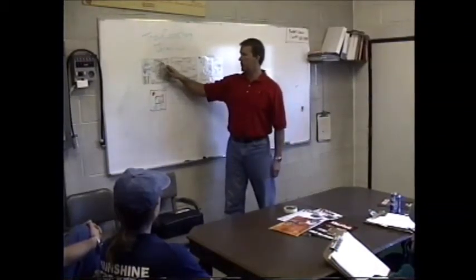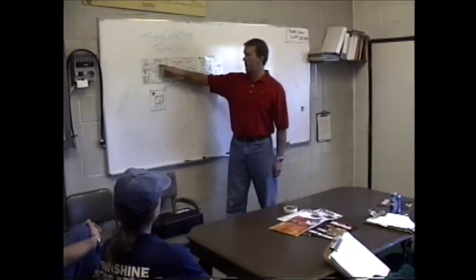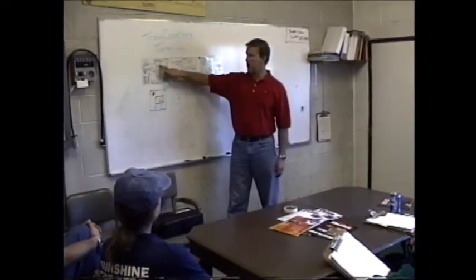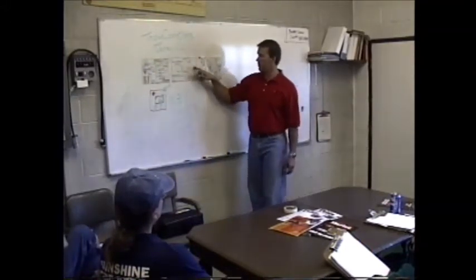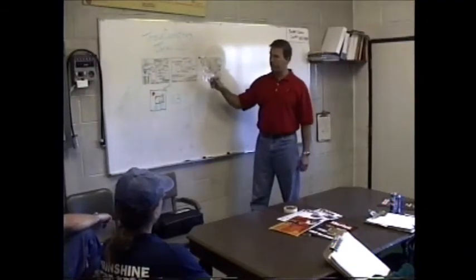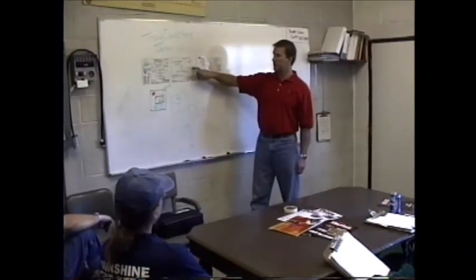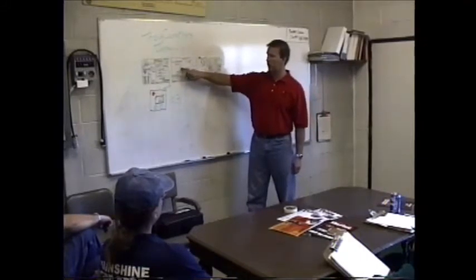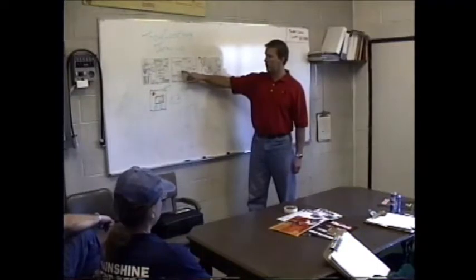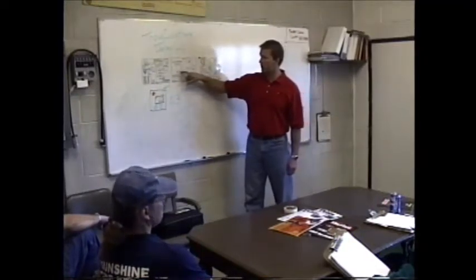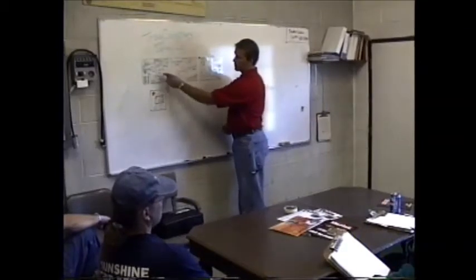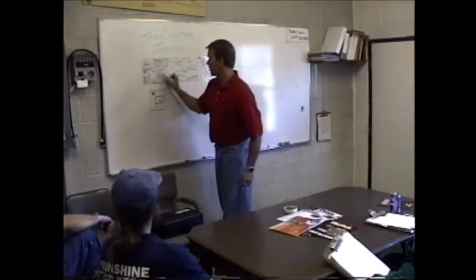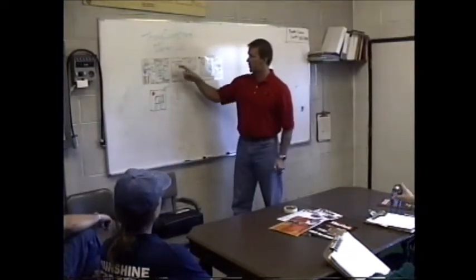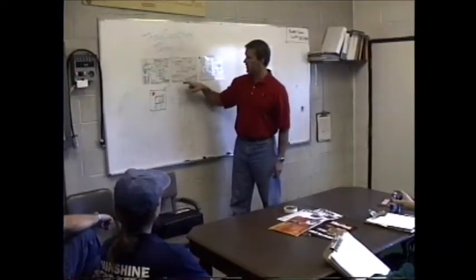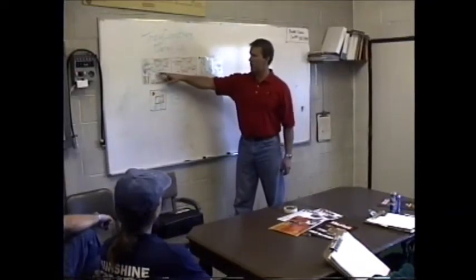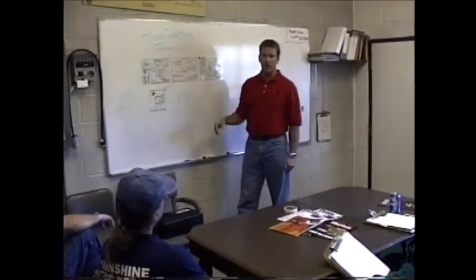And what these lines show is two different options. You can either have an inline valve that's preset with an electric toggle switch control valve, where on the pump panel what you see is your control valve for adjusting your water foam solution, and then a toggle switch above it. What that toggle switch does is it sends an electrical signal to an electric valve that opens the airflow in through a check valve and into that pipe where that foam water solution is coming through. This is a blown up version of what you see right in here, okay? It's just showing it the opposite direction. But you'll take air through a solenoid valve, it injects into that check valve right here, and then that foam water solution travels through that pipe and mixes with the air, and out the end comes compressed air foam.